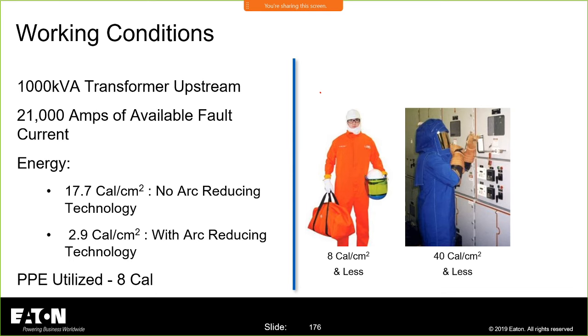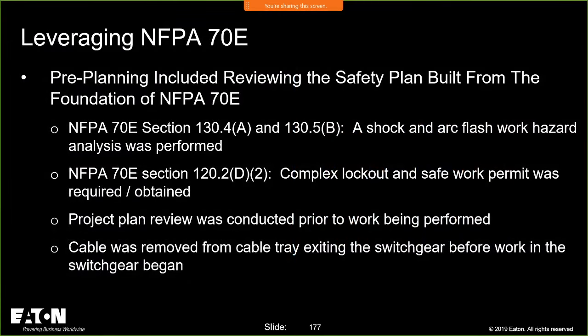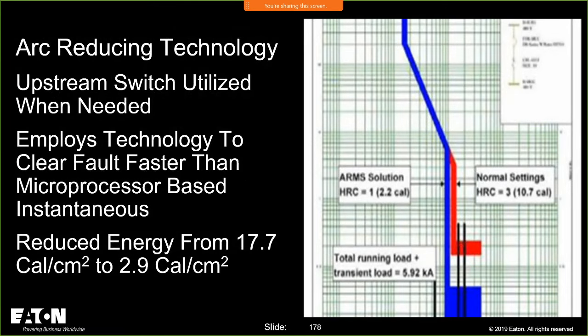So in this case, they were wearing the 8-calorie outfit, but they knew they had 2.9 calories of incident energy at this equipment. They did everything that they were supposed to do. They did the lockout tagouts. There was a complex lockout tagout procedure to de-energize, and they activated the arc reduction maintenance switch, which included a lock and tag out to make sure that nobody turned it off. They got everything ready for the work. The arc reduction maintenance switch gets them down to a very low value of incident energy.